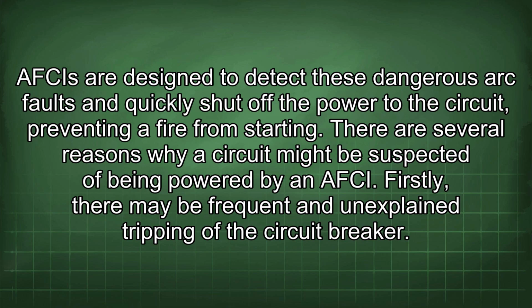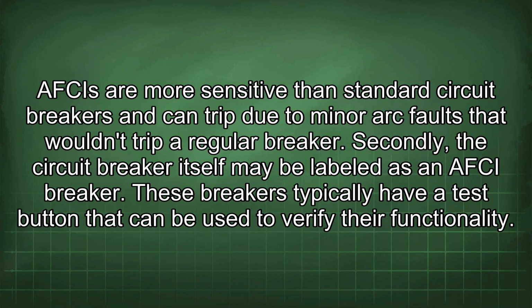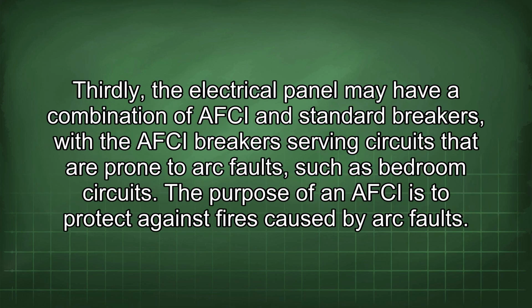There are several reasons why a circuit might be suspected of being powered by an AFCI. Firstly, there may be frequent and unexplained tripping of the circuit breaker. AFCIs are more sensitive than standard circuit breakers and can trip due to minor arc faults that wouldn't trip a regular breaker. Secondly, the circuit breaker itself may be labeled as an AFCI breaker. These breakers typically have a test button that can be used to verify their functionality. Thirdly, the electrical panel may have a combination of AFCI and standard breakers, with the AFCI breakers serving circuits that are prone to arc faults, such as bedroom circuits.